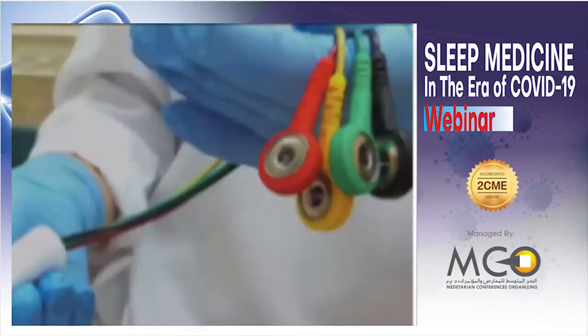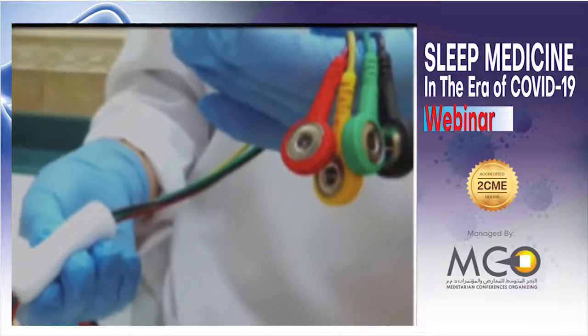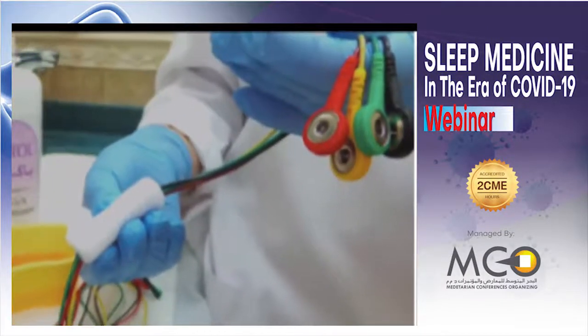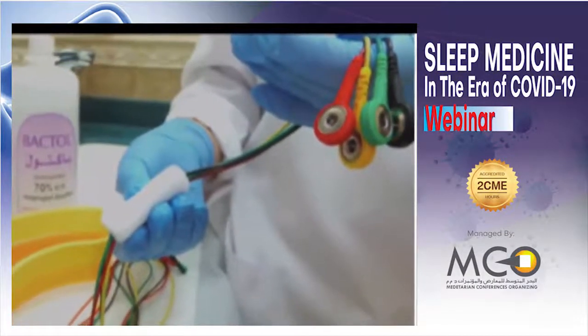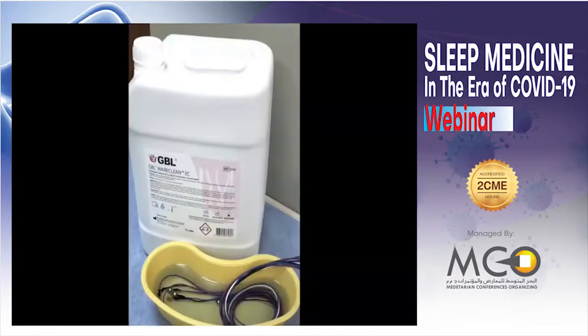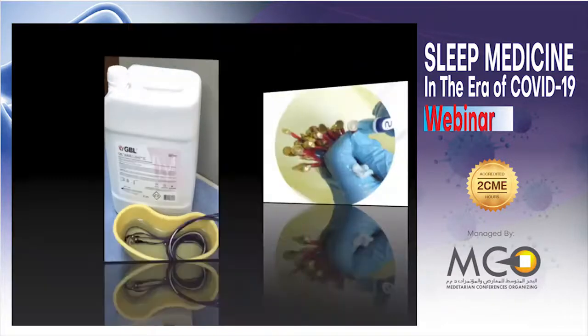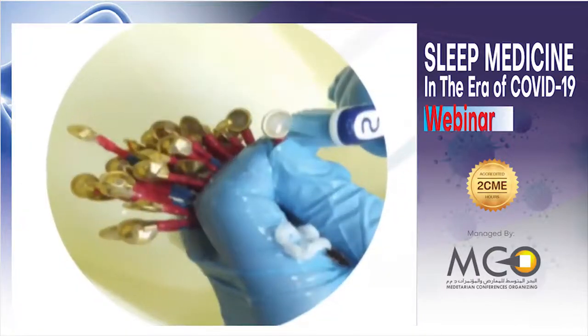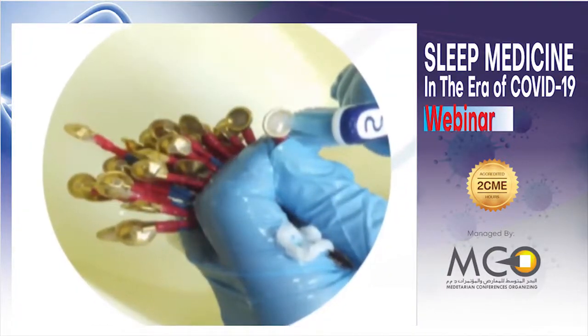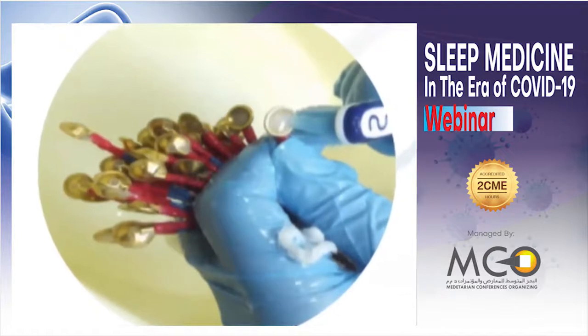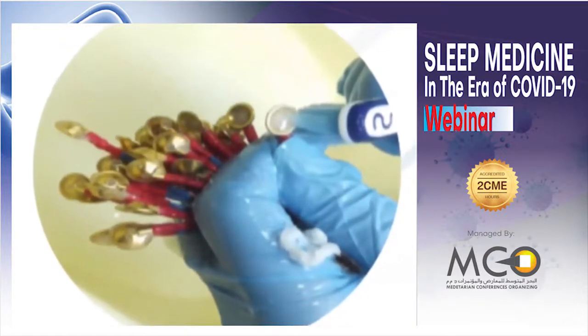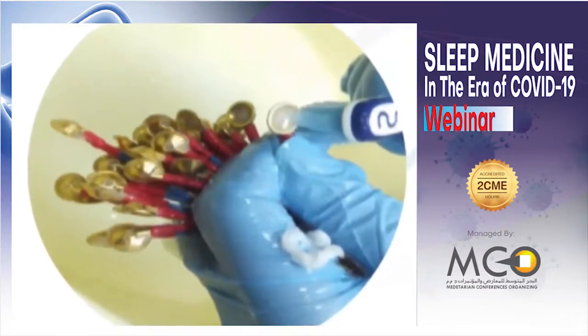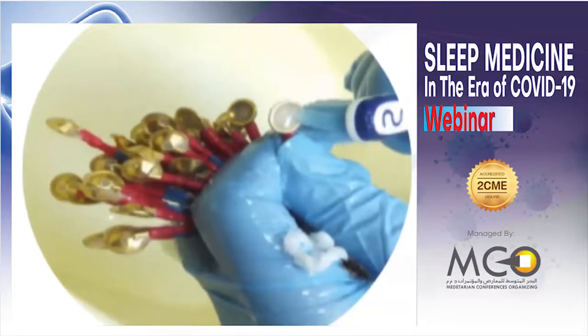Body position sensor and snap electrodes such as ECG and leg EMG. Clean the sensor with a soft, wet cloth with 70 to 90% isopropyl alcohol. Gold disc EEG electrodes. Soak in general disinfectant according to the manufacturer's directions after each use. Brush and rinse with warm water, and then you may disinfect them with sodium hypochlorite, Cidex OPA solution, or activated glutaraldehyde such as Cidex and Metricide.